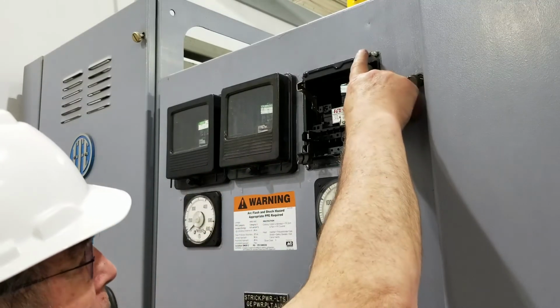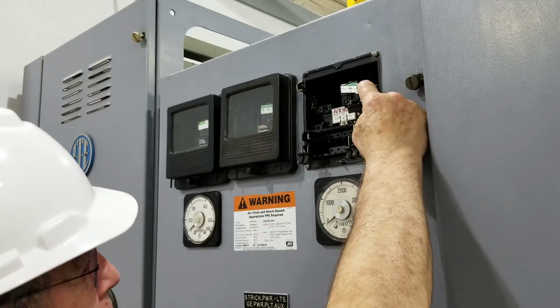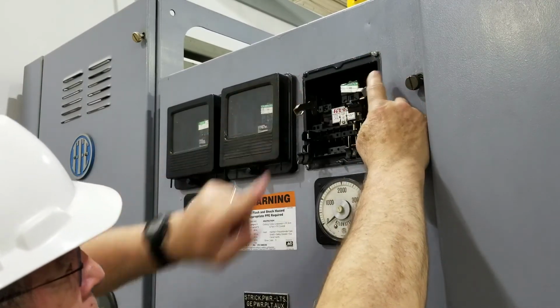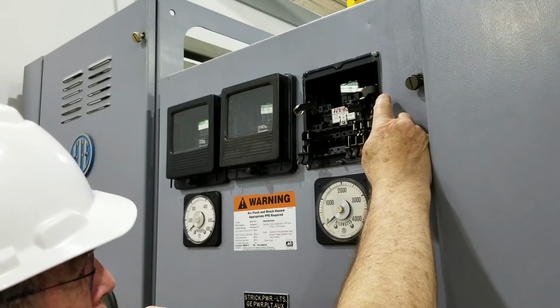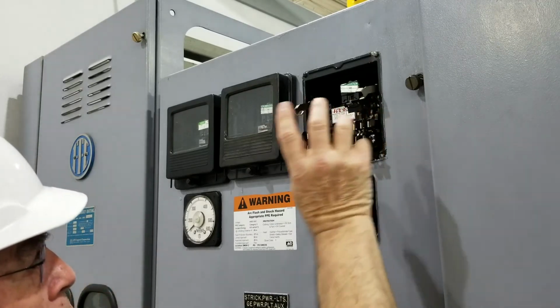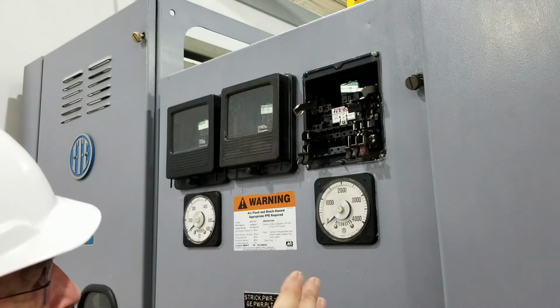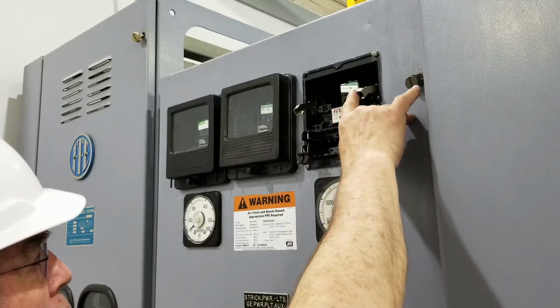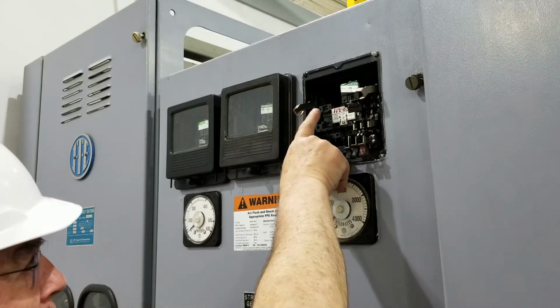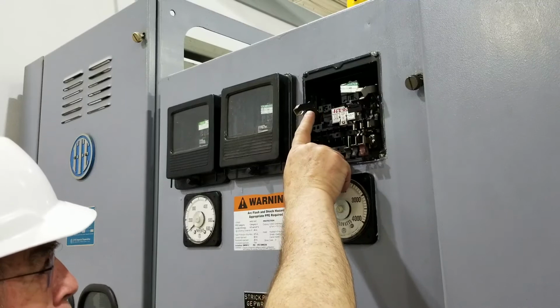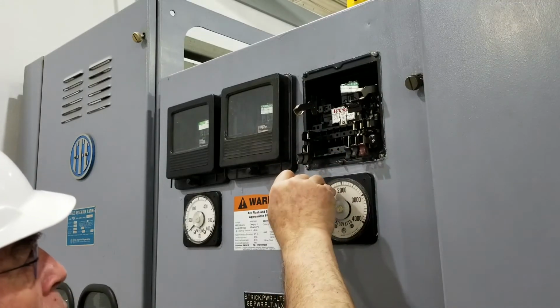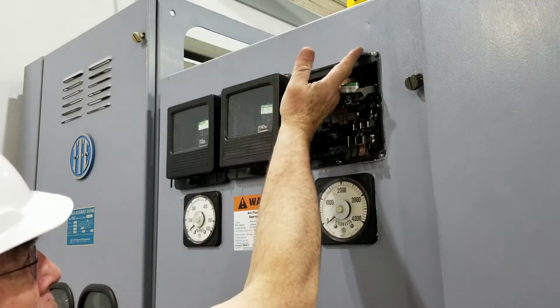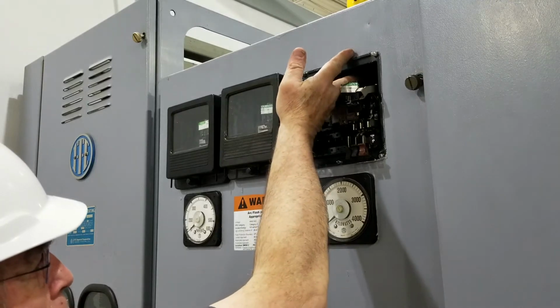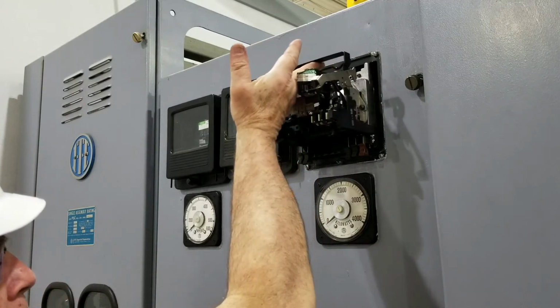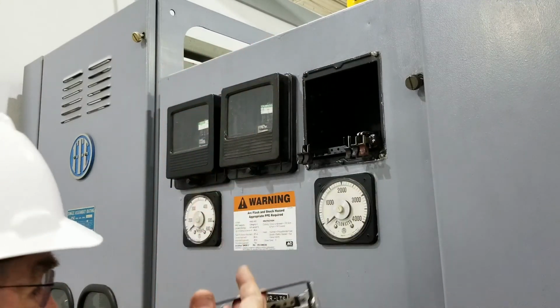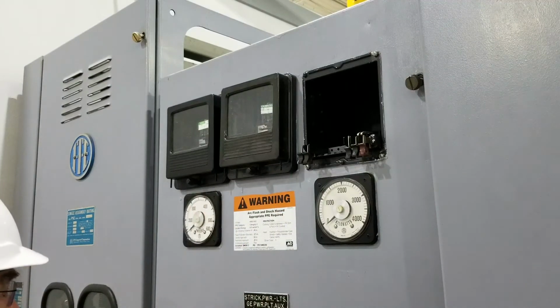Once we've got our switches open, the next thing we do is pull down on the connecting latches, this one and this one, and our relay is ready to be removed. Like the GE relay, we're not going to grab any component of the relay, such as the seal-in unit, or an instantaneous unit if it had one, to pull the relay out. What we do is put our finger up here and slide it right underneath the support bar on the frame and simply slide it out and set it on our test bench.